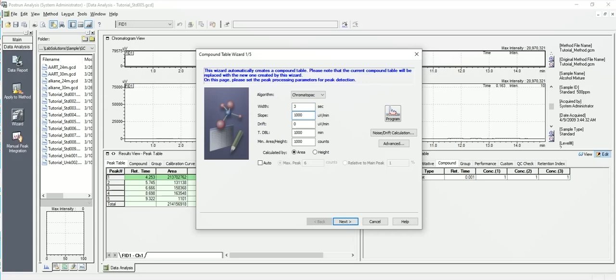It's how wide a peak needs to be, but that's not used as frequently as peak slope. The slope here is also sometimes called the threshold. It's a change in the rise in the baseline at which it says hey, this is no longer noise, this is actually the start of a peak. So I make this very small we will see lots of peaks. If I make it very big you will only see a few peaks.